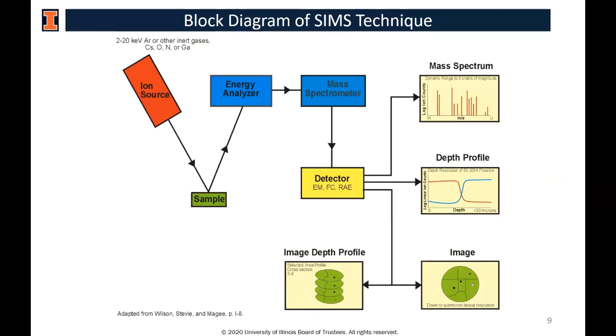This slide shows a generic block diagram of the SIMS instrument. There is an ion source for the primary ion — cesium and oxygen are traditionally used for semiconductor work, while gold and bismuth are used for other analyses. The sample must be vacuum compatible and is best if conducting, though low-energy electron and ion guns allow some insulating samples to be measured. The secondary ions are accelerated through an energy analyzer and mass spectrometer to a detector, yielding mass spectra, depth profiles, ion images, and 3D ion image depth profiles.